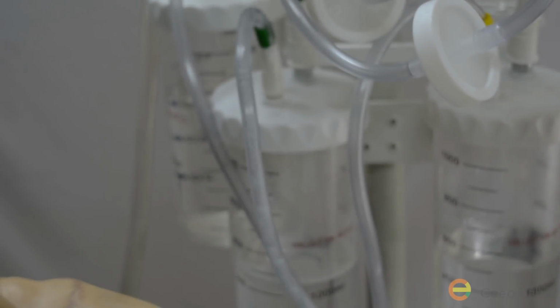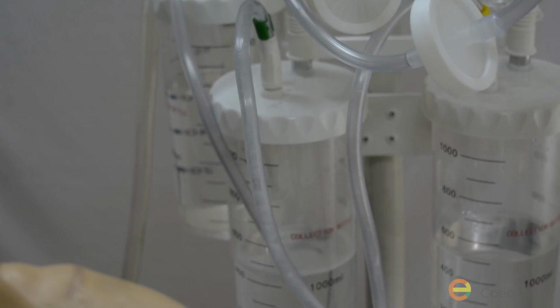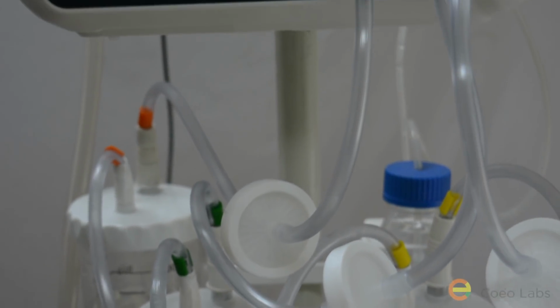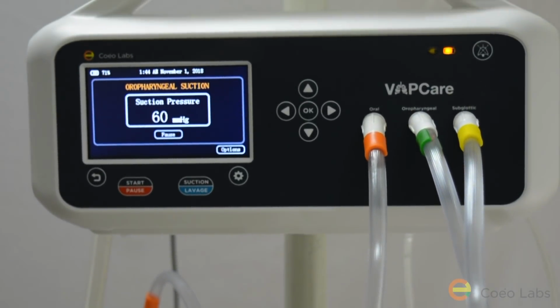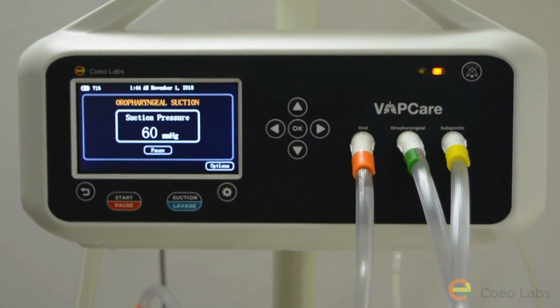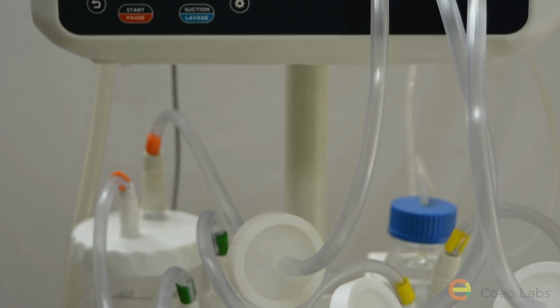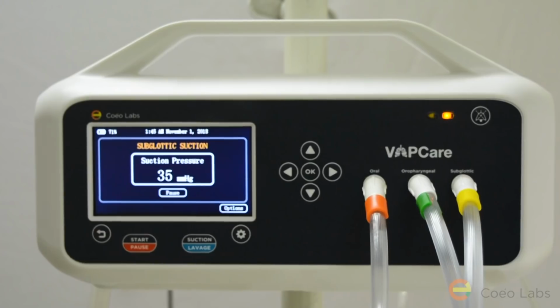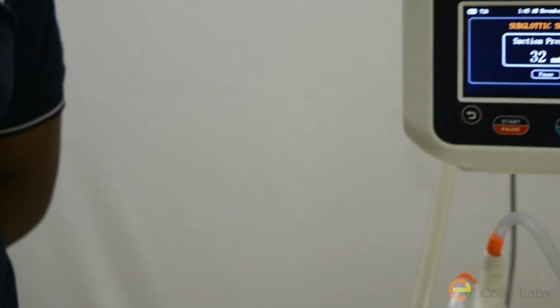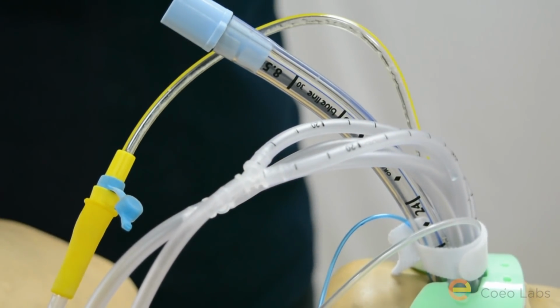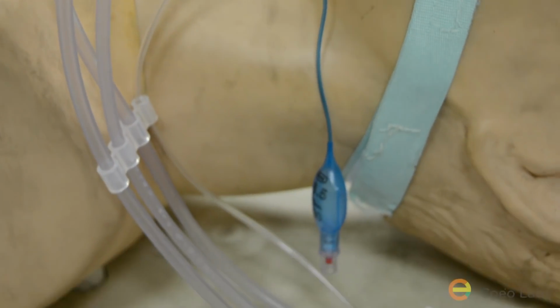This suction cycle will continue to the maximum of 1 minute till the secretions are present. If the secretions are absent, the suction cycle will go to the next cycle after 13 seconds. Now here you are seeing that there are secretions coming out from the oropharyngeal region, so that's why the suction is going on. You can see in the subglottic suctioning, the device is collecting fluid from the subglottic. In this case, for the sake of demonstration, we have instilled additional fluid into the oropharyngeal and subglottic region.